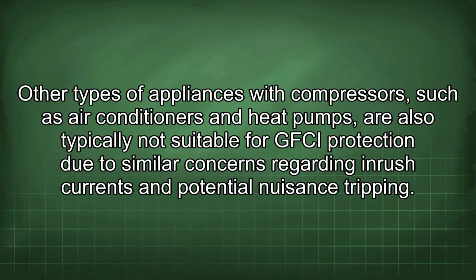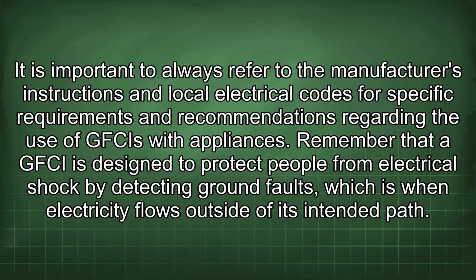Other types of appliances with compressors, such as air conditioners and heat pumps, are also typically not suitable for GFCI protection due to similar concerns regarding inrush currents and potential nuisance tripping. It is important to always refer to the manufacturer's instructions and local electrical codes for specific requirements and recommendations regarding the use of GFCIs with appliances.